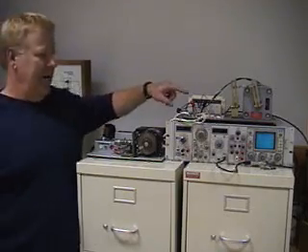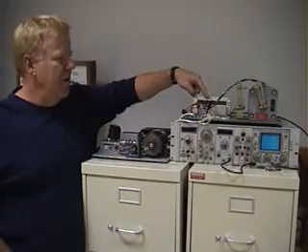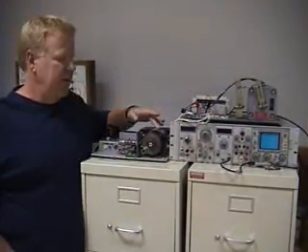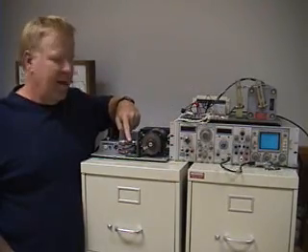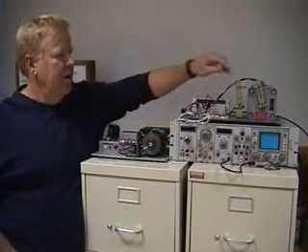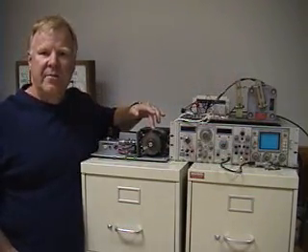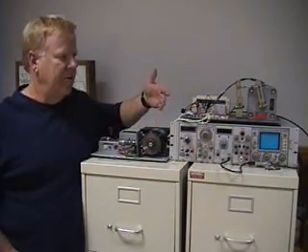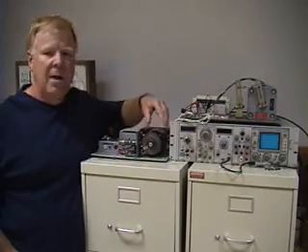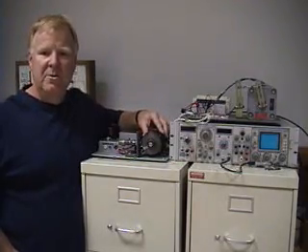What we have here is a closed-loop speed simulator with a speed control here driving an all-electric actuator. The speed control is getting its speed signal from a magnetic pickup. Controller here is driving a DC motor, so as the speed control requires more fuel, it's going to send a higher DC voltage to drive it faster. As it needs less fuel, it's going to give it less DC voltage and it's going to slow it down. So we have a complete closed-loop system here running speed control.